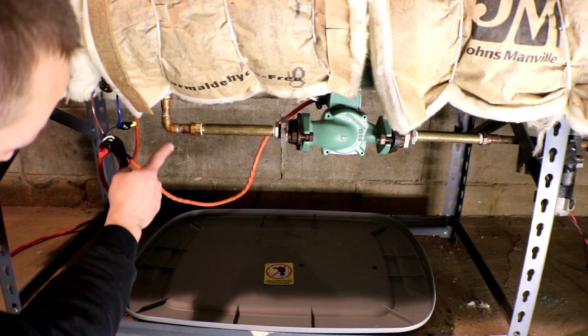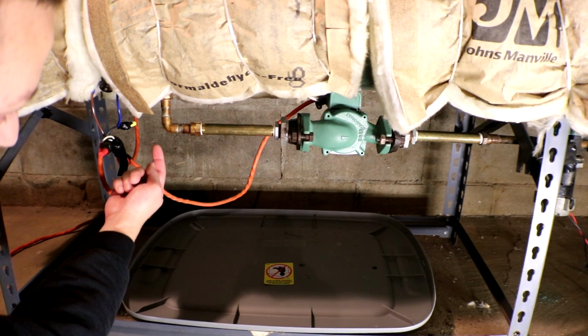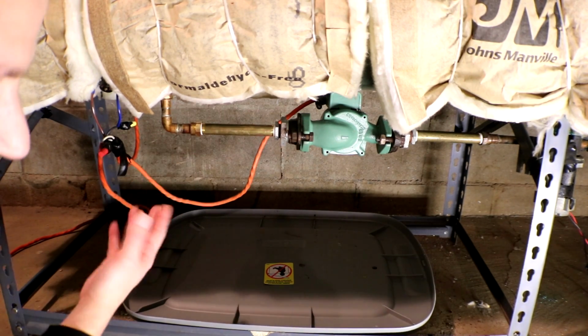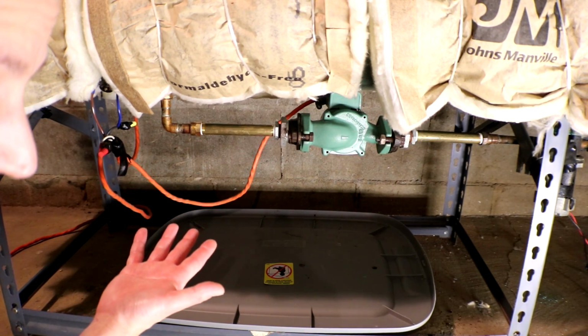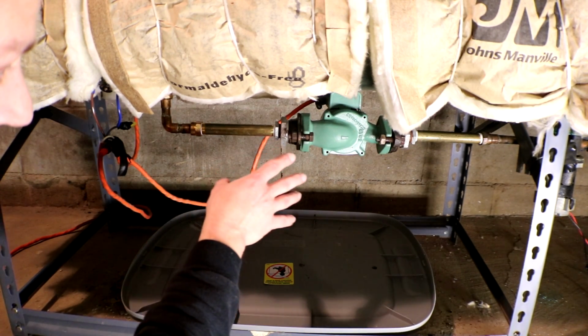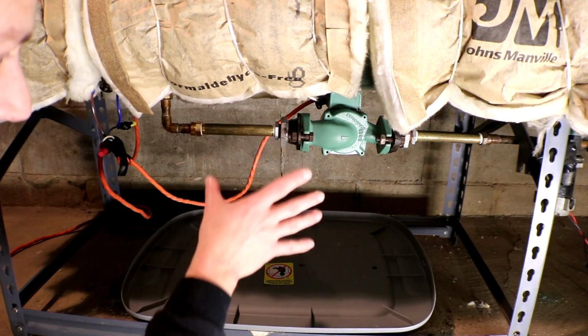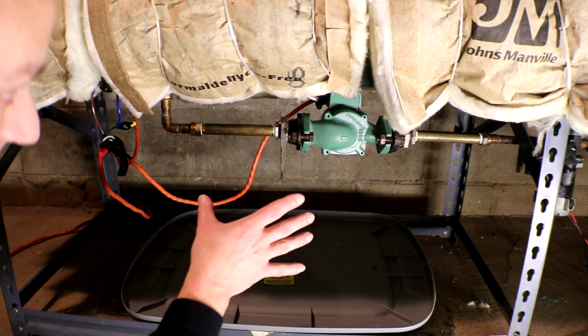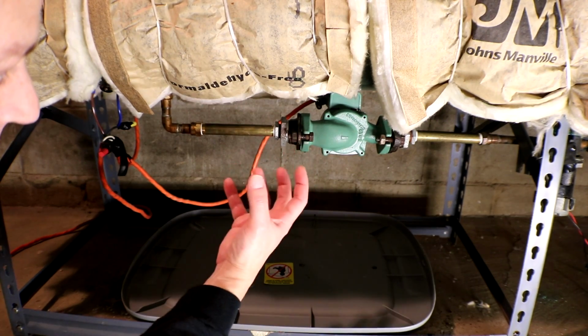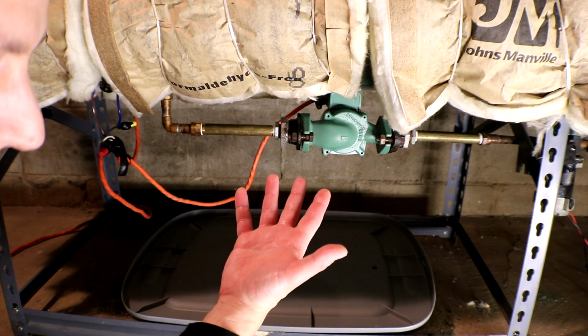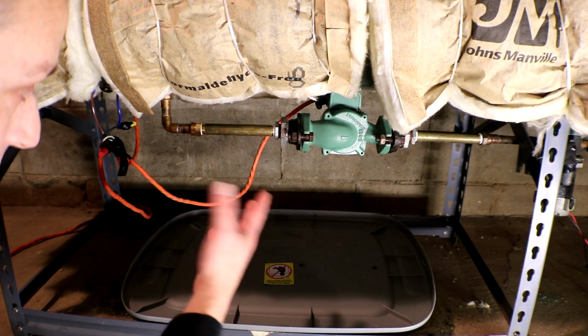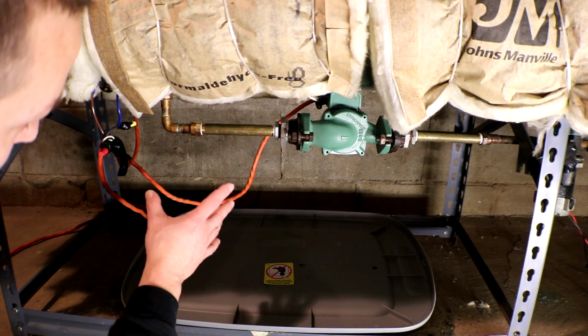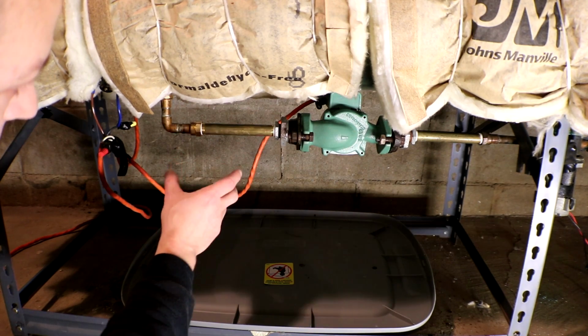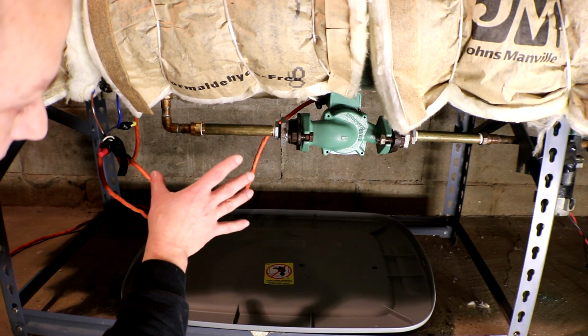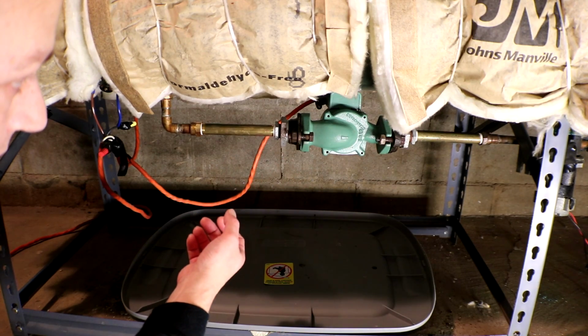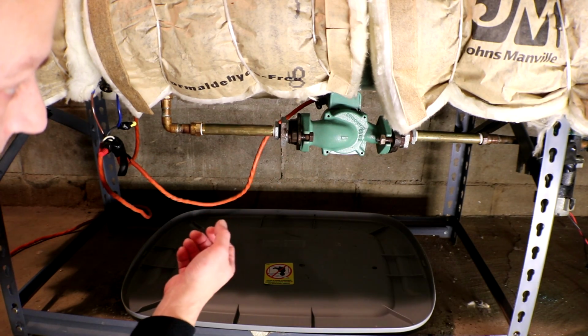This side I probably should have put a piece of brass right before it goes into the tank, because the tank is made out of steel. I don't know if it's lined with anything, no clue, but I think that was part of the reason this pump went out - too much electrolysis happened in the system, and the pump's impeller was full of gunk, basically rust or elements pulled out of the system. So I probably need some sort of dielectric coupling down here to separate the system a little better, which I'll do sometime in the future. I just haven't done it yet.